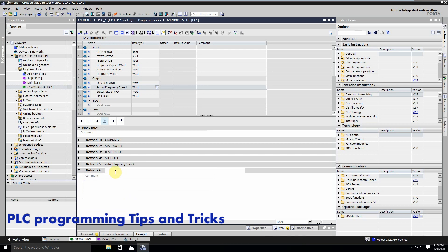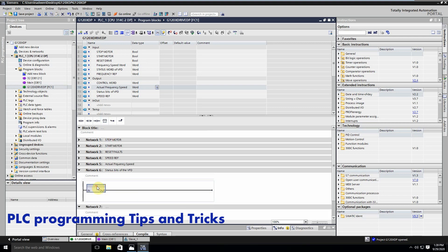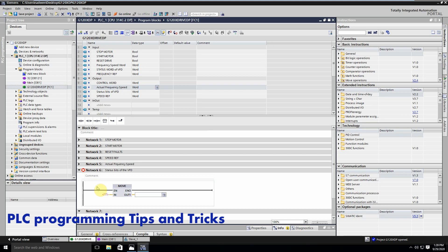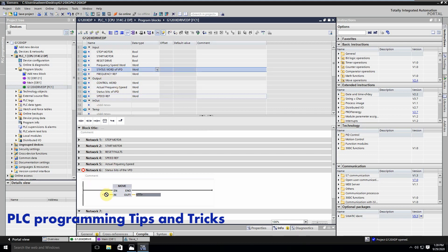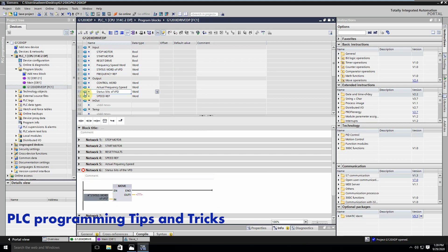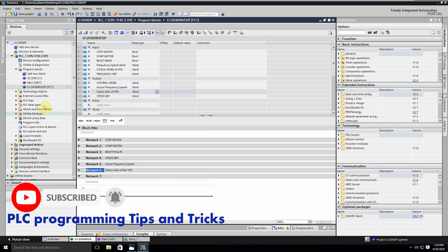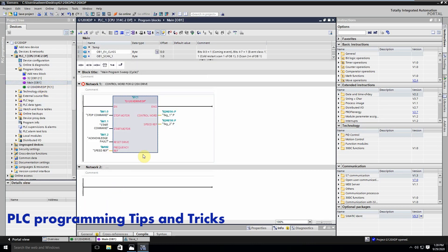In Network 6 we will write the code to transfer the status bits to the output word. We use a Move command here and drag and drop the status word of the VFD on the input. For the output we drag and drop the status bits word. Whatever data is coming in the status word of the VFD will go into the status bits word.